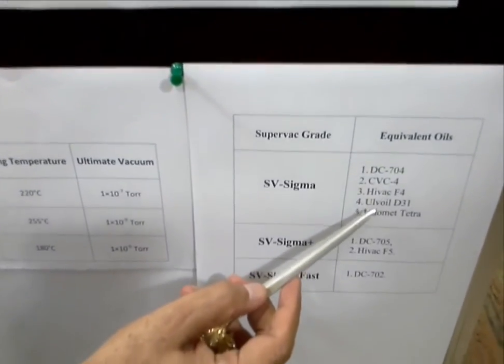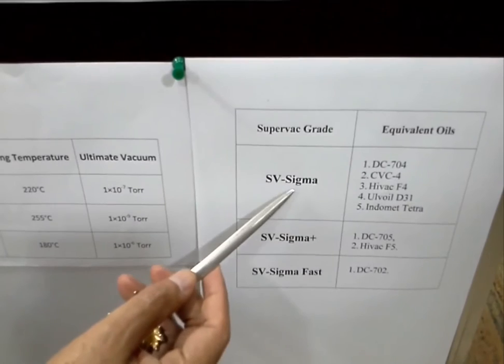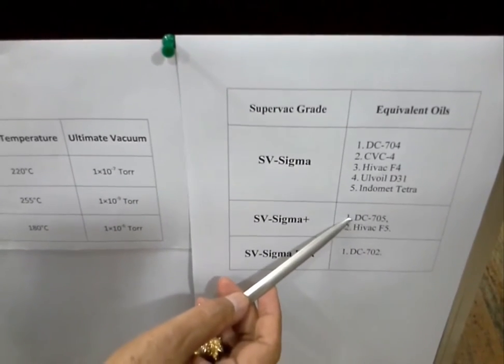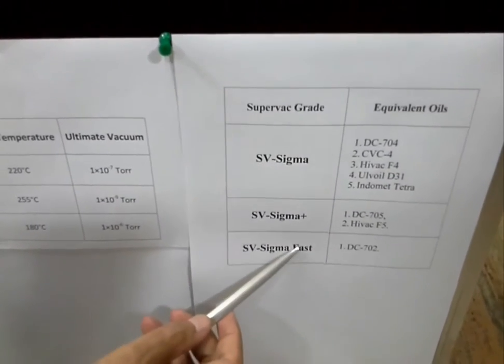This understanding of boiling temperature gives us another advantage. Suppose a manufacturer is charging you very high for a diffusion pump oil, or the oil recommended by the manufacturer is not available in your country or region. You can always choose an equivalent diffusion pump oil based on the boiling temperature being recommended to you. For example, if you are using any of these oils — DC704, CVC4, Hivac F4, Ulvoil D31 — you could use SV Sigma. These oils will give all the same working parameters: vacuum level, working life, vacuum everything, but they will be cheaper — some much cheaper.